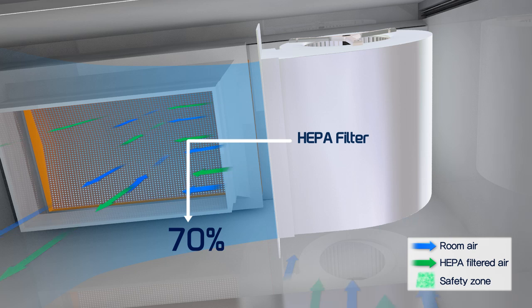70% of total air through the blower will be recirculated to the chamber through supply HEPA filter. And 30% of total air will be exhausted outside through exhaust HEPA filter.